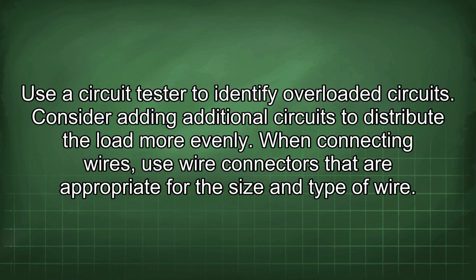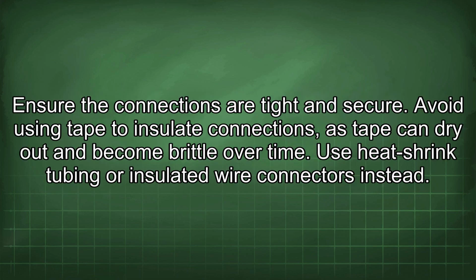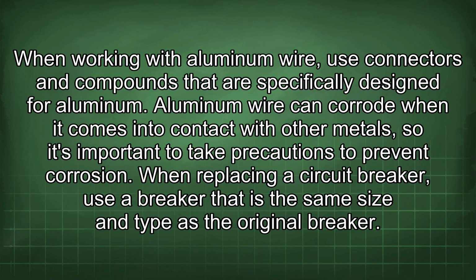When connecting wires, use wire connectors that are appropriate for the size and type of wire. Ensure the connections are tight and secure. Avoid using tape to insulate connections, as tape can dry out and become brittle over time. Use heat shrink tubing or insulated wire connectors instead. When working with aluminum wire, use connectors and compounds that are specifically designed for aluminum. Aluminum wire can corrode when it comes into contact with other metals, so it's important to take precautions to prevent corrosion.